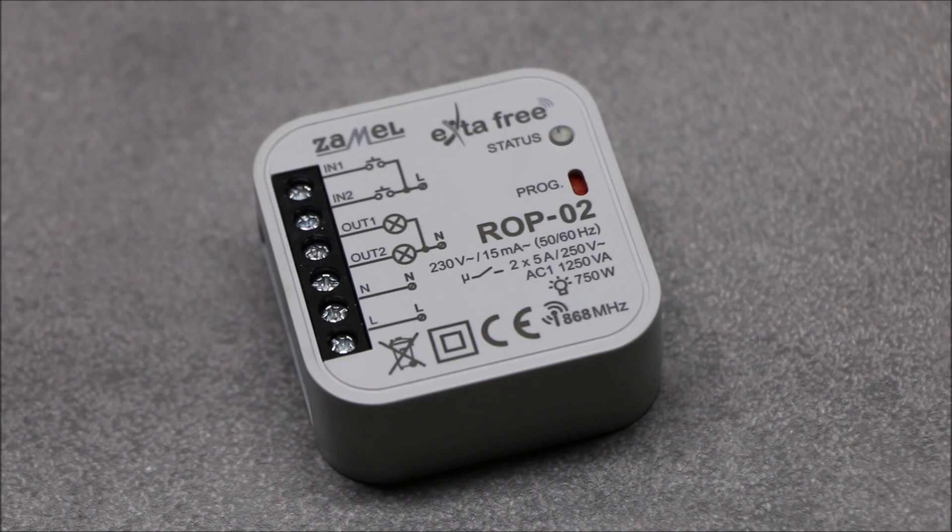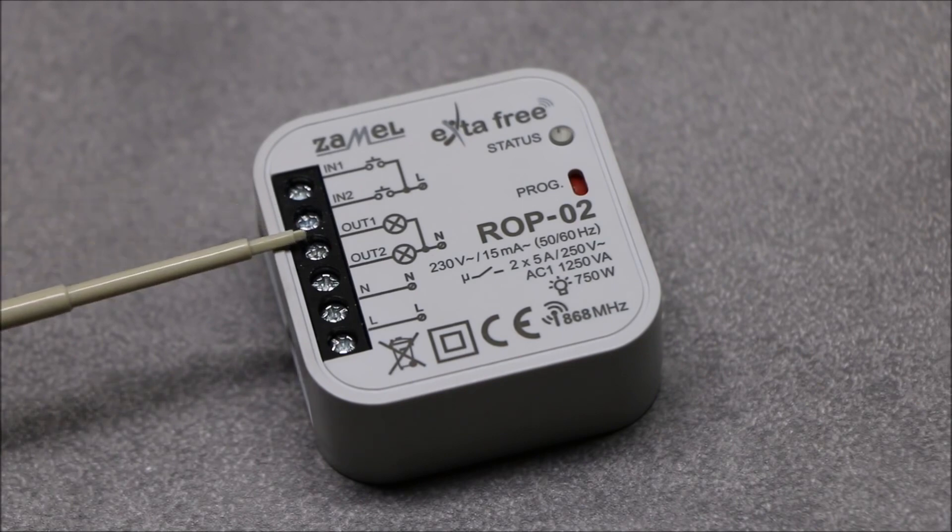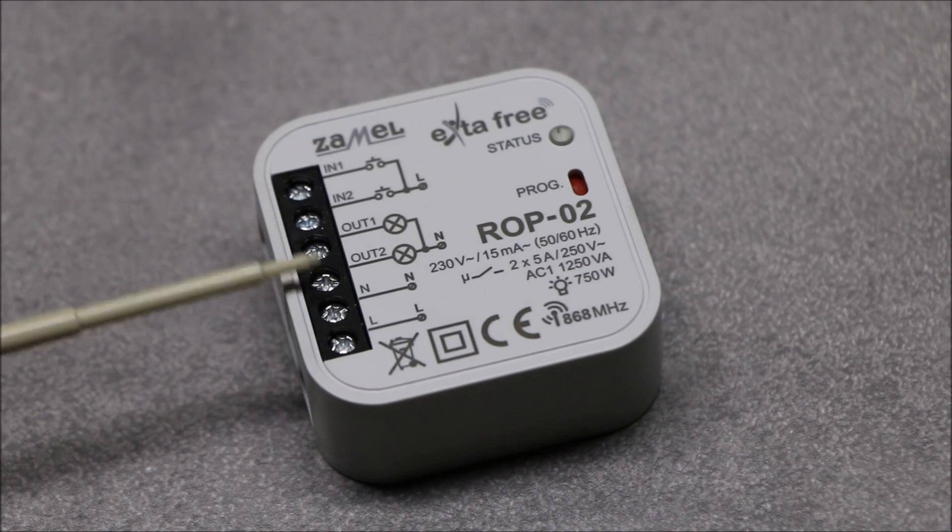ROP02 is the receiver of the Exta Free wireless control system. It is designed for remote switching on and off of light sources and other devices powered by 230 volts AC. The receiver's unique feature is two outputs, which allow independent control of two circuits. Phase signal is available on the OUT1 and OUT2 output terminals; therefore outputs are voltage type, powered with 230 volts AC.